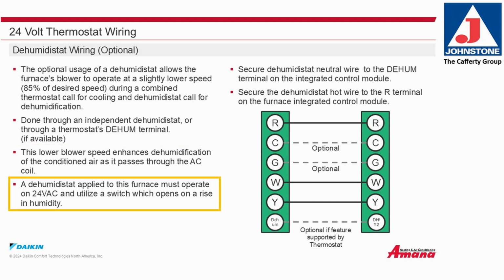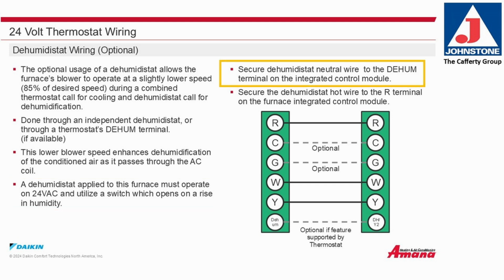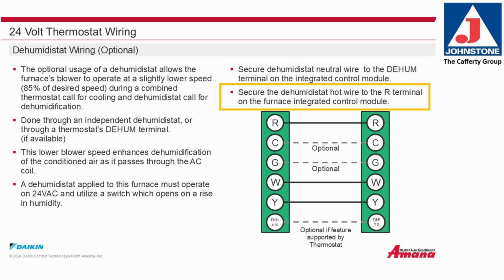A dehumidistat applied to this furnace must operate on 24 volts AC and use a switch that opens on a rise in humidity. Connect the dehumidistat neutral wire to the dehumidification terminal on the integrated control module. Connect the dehumidistat's hot wire to the R terminal on the furnace's integrated control module.